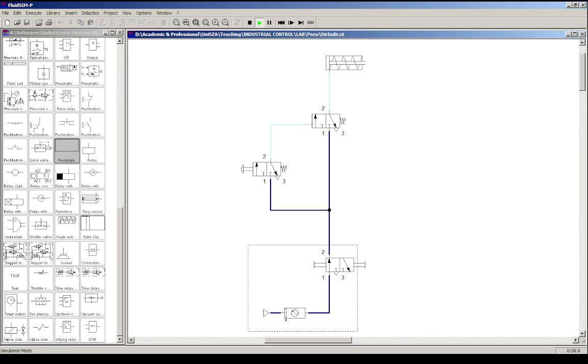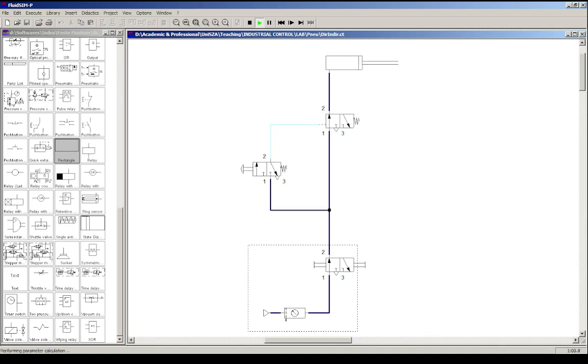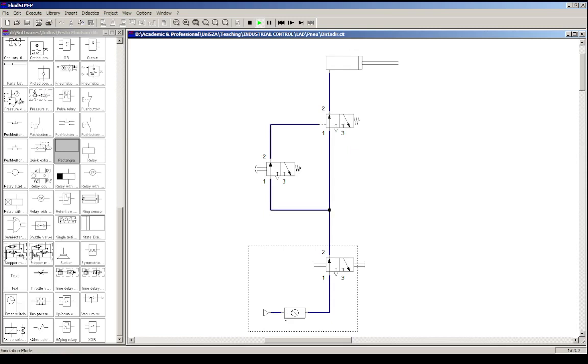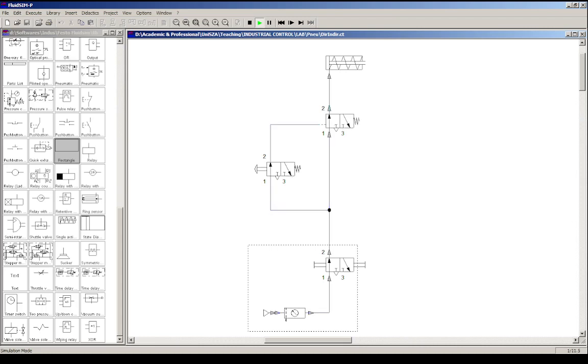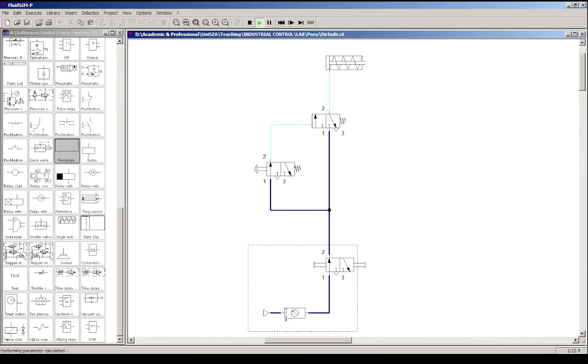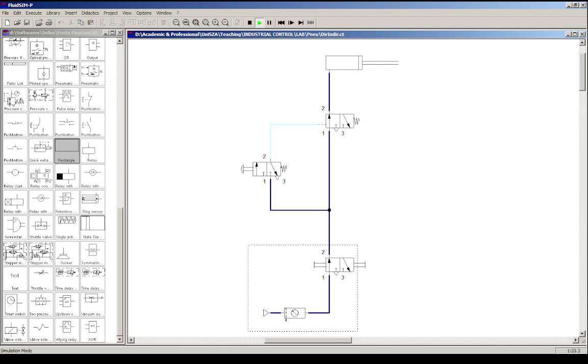The piston goes back to home position. Activate again, release, activating again, release. Just one interesting note: the valve over here is actuated manually, whereas the valve here is actuated pneumatically. There is no human operator that pushes this valve - in fact, air that is leaving the valve here goes all the way to actuate the intermediate switching valve.